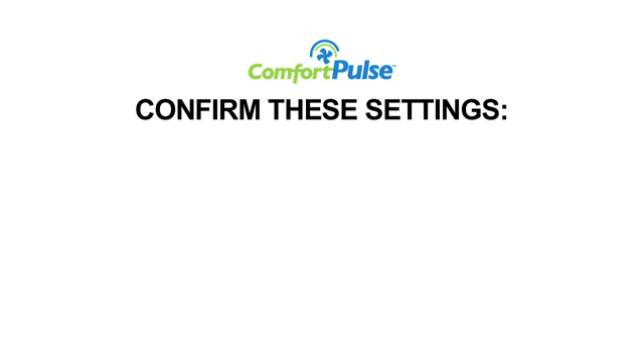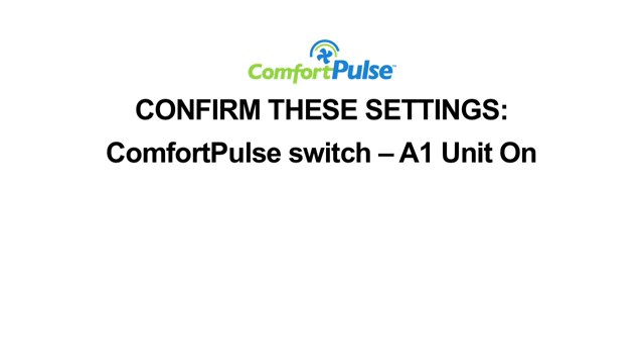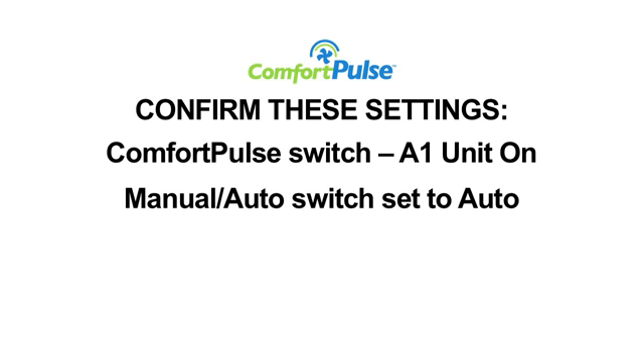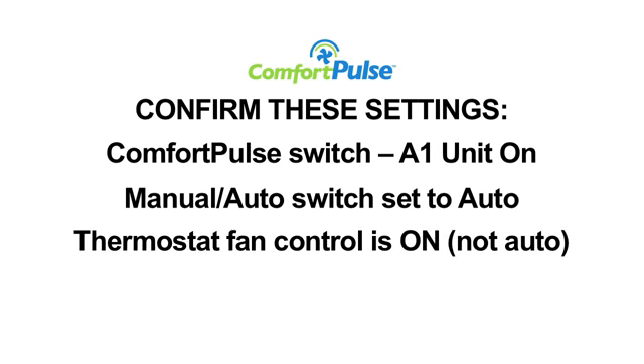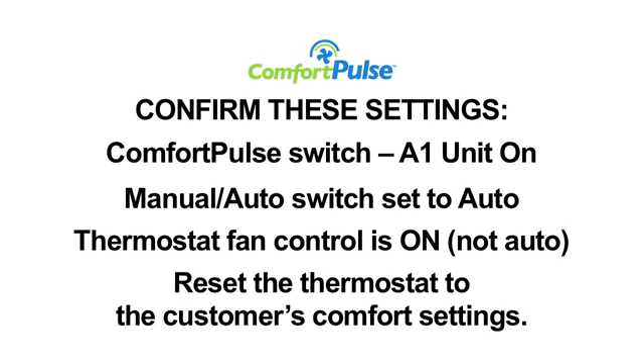Finally, confirm these settings. Comfort Pulse switch, A1 unit on. Manual auto switch set to auto. Thermostat fan control is on, not auto. Reset the thermostat to the customer's comfort settings. This concludes the Comfort Pulse installation guide video.